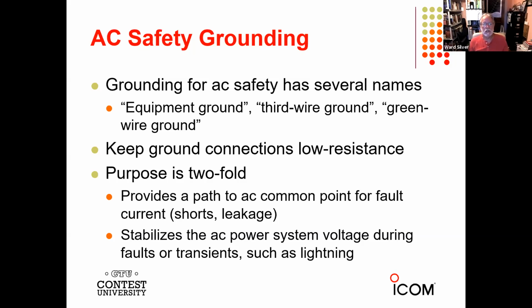It also stabilizes the AC power system voltage during faults or transients, such as when lightning hits a power pole, or there's an auto accident or something. All those connections to ground rods and butt wraps around the pole stabilize the power system so the voltage doesn't swing around wildly. So there's only two reasons for this AC safety ground, and those are it. Neither have anything to do with RF, and they are not really very effective at lightning protection in your station.